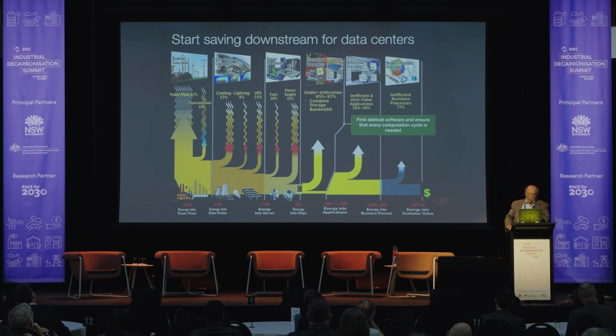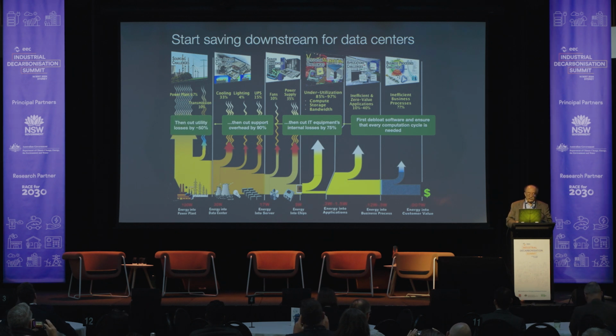Then you can at least quadruple, nowadays more, the server's efficiency, and they'll need a lot less cooling and power supply, both of which can be done in smarter ways. And then we could even save half the utility losses with fuel cell trigeneration, cheaper than the UPSs it displaces. If you multiply these savings from downstream to upstream, you cut energy use by at least two orders of magnitude. In the project for which we made this diagram in 2009, the client rejected most of our recommendations, so we were only able to treble efficiency at the same capex.